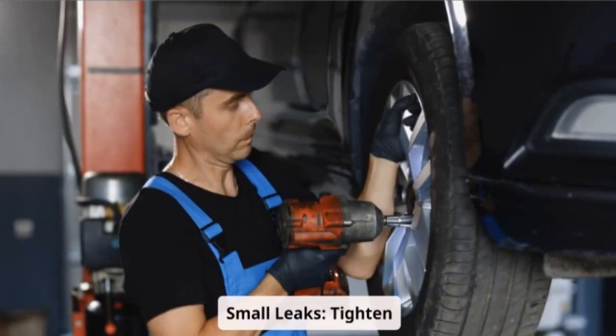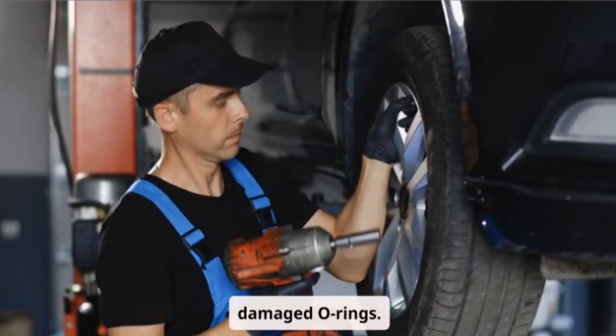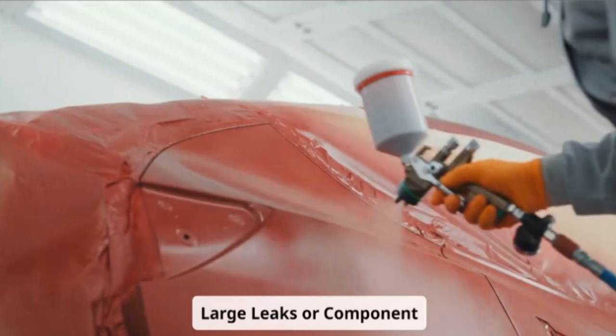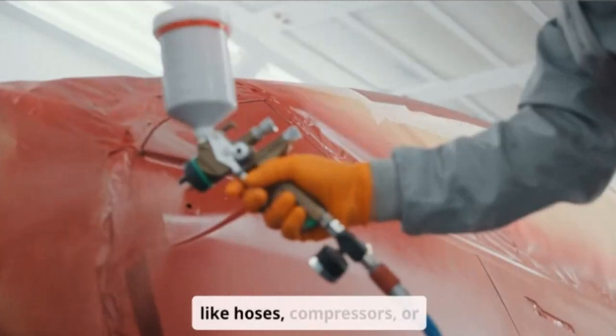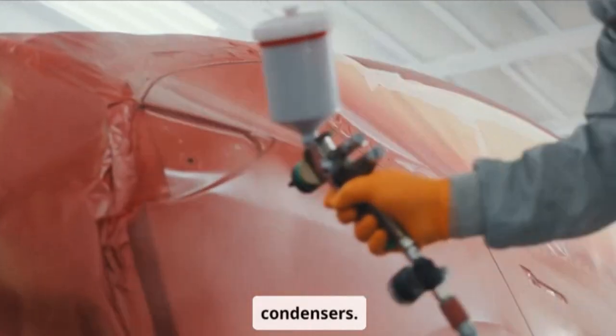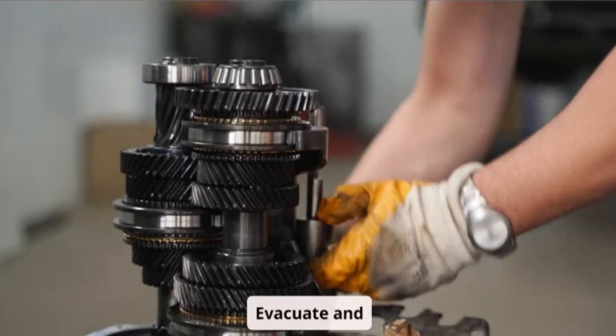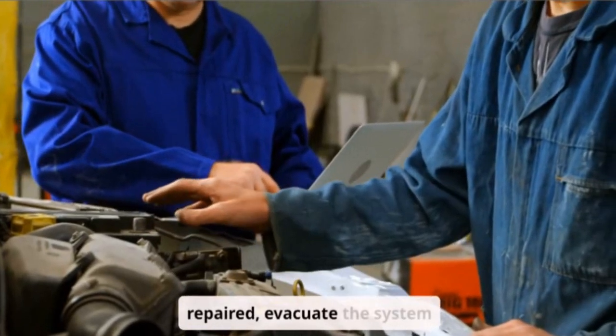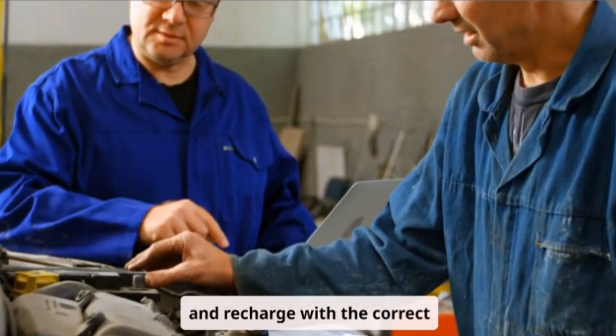For small leaks, tighten loose connections or replace damaged O-rings. For large leaks or component damage, replace faulty parts like hoses, compressors, or condensers. Evacuate and recharge. Once the leak is repaired, evacuate the system and recharge with the correct amount of refrigerant.